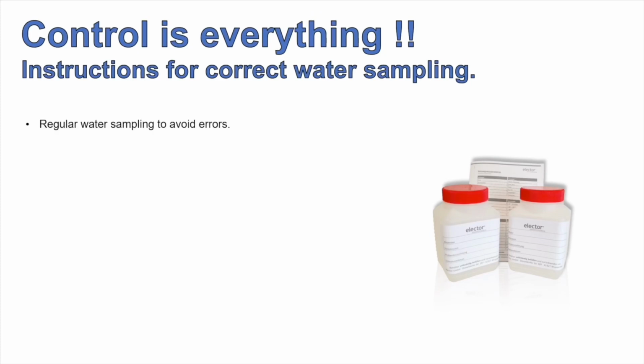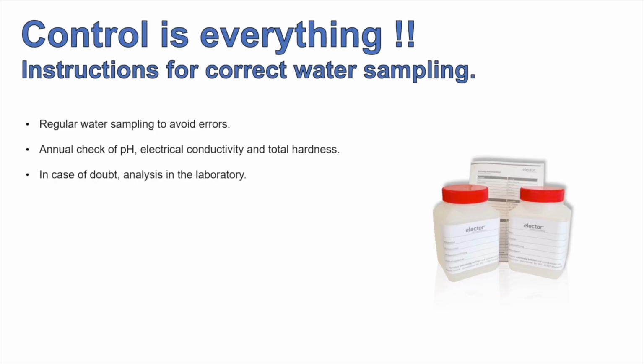Control is everything. We need to make sure that we're checking our water on our services. So regular water sampling to avoid errors, annual check of the pH, electrical conductivity and total hardness. If you have any doubt, send the sample to a lab. Always take it in a good place where we've got steady flow of water.